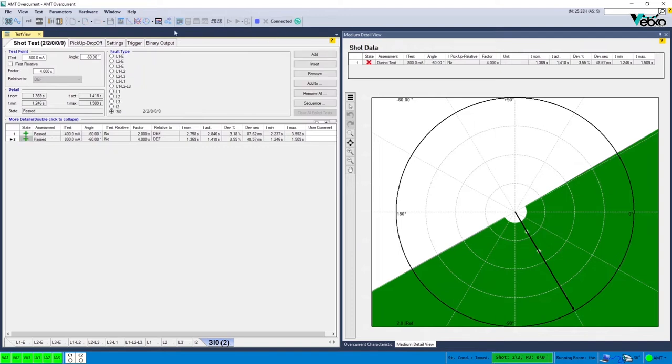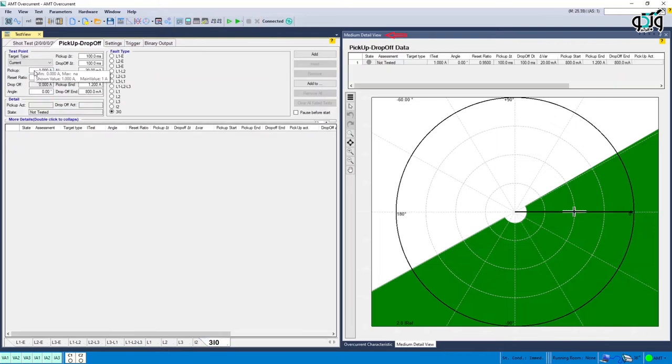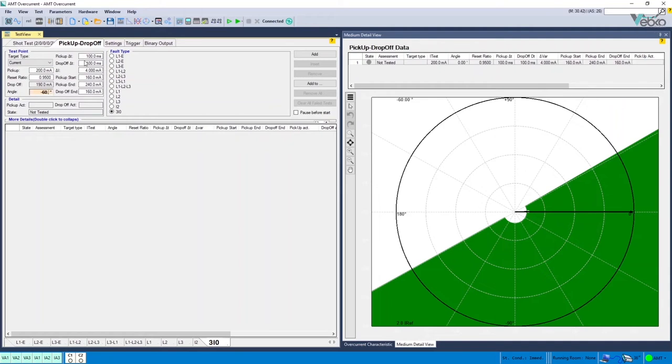The next step is to enter the current setting and the angle in Pickup and Dropoff section. To do this, Medium Detail View window can be used which gives a complete indication of the characteristic. The process of specifying Pickup and Dropoff can be completed first for the current value and then the angle values.